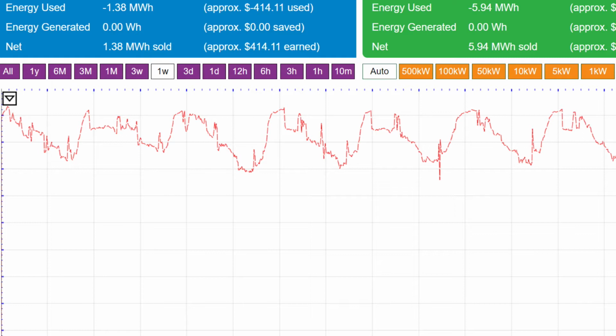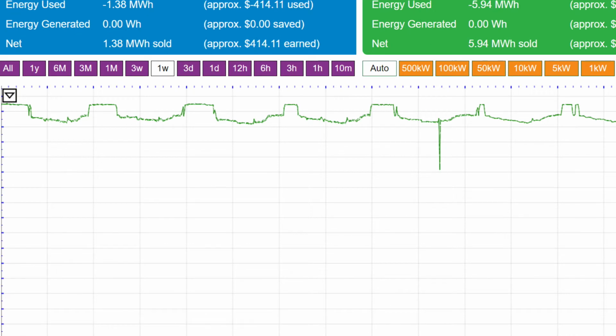If you could please go to the next screen. Yeah, this is that same week. This is showing amp deflection, or how many amps are being used. So normally a unit like this would run at around 60 to 62 amps. This unit is running fairly steady between a low of 14 amps and a high of 16 amps. This is unheard of. This unit, which is supposed to be running at around 60 amps, is running consistently between 14 and 16 amps. This is savings on a scale never before seen in air conditioning.